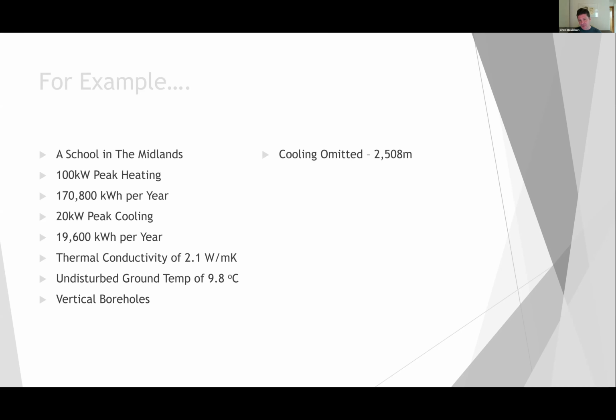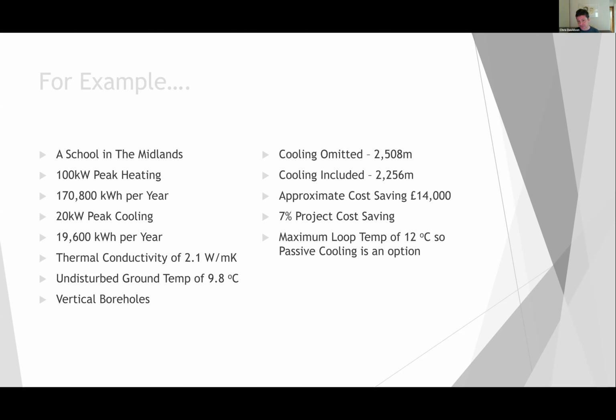If we now add that cooling demand in, then we reduce the requirement using the same temperature profile in the ground. We reduce that requirement to 2,256 meters, which is obviously a significant saving. To put that in monetary terms, we're saving about £14,000 on this project, which would equate to about 7% of the project install cost for the system being saved by including that cooling. In addition to that 7% saving, which is purely on the drilling, we would also be saving because we wouldn't be putting conventional cooling equipment on the building. So there would be additional cost savings involved as well.